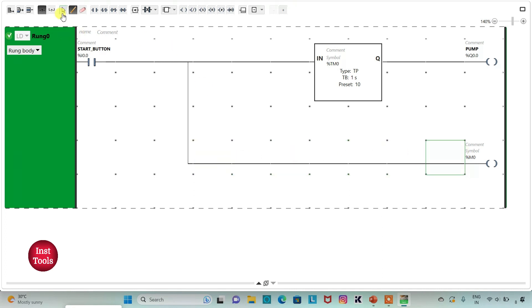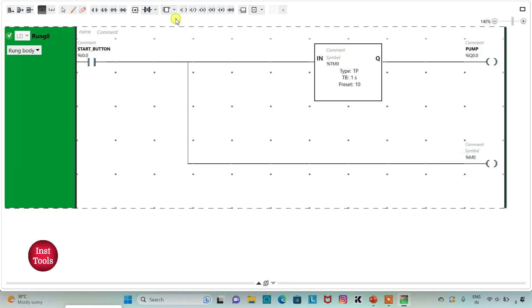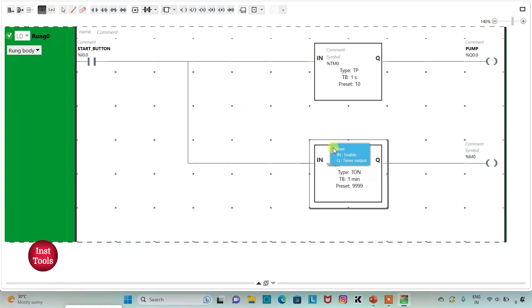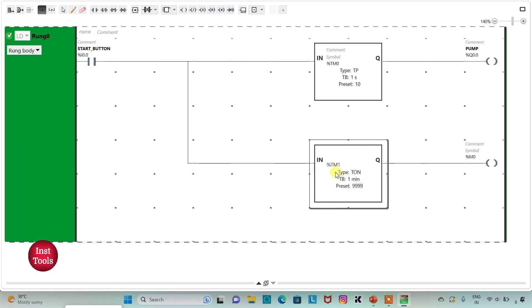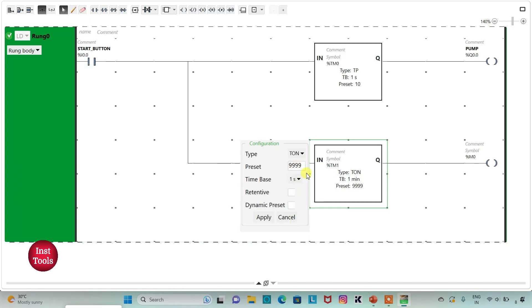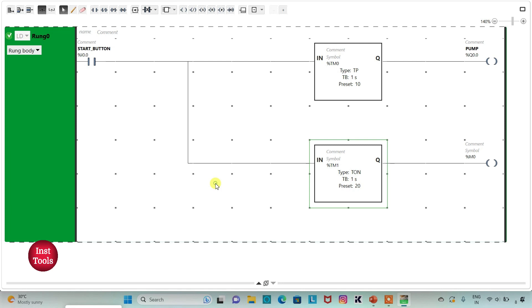Then I will insert one more timer to turn off the pump. The type of the timer should be TON, and then I will change time base to 1 second and preset value as 20, then click on apply. So this timer will turn off pump for 20 seconds.